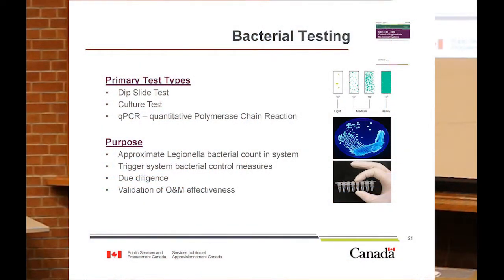So the test types that we use are dip slide testing for general bacteria, Legionella culture testing, which will give you detections of living Legionella within your system, as well as the use of quantitative polymerase chain reaction testing, or qPCR, a DNA-based test that'll give you presence of living and dead Legionella in your system. So I'll talk a bit about when we use those. It's a little bit different than culture testing.